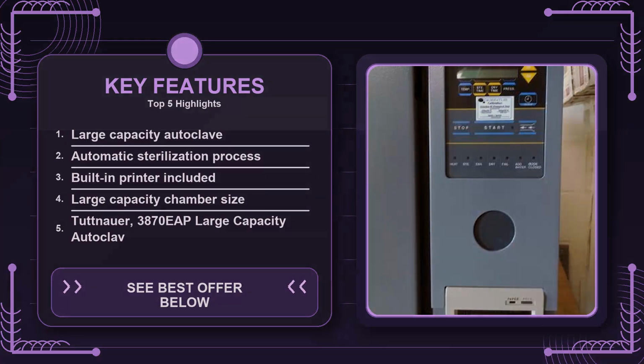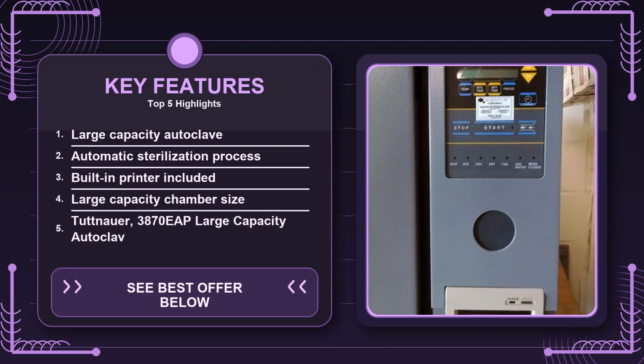However, the machine's cycle times are a bit longer than some of the newer, more compact models that boast rapid heat technology. In practice, you'll be looking at a typical sterilization run of around 30 to 35 minutes for a full load. If your workflow depends on turning around instruments within 10 minutes, you'll feel that lag. Conversely, if you can schedule your sterilization in batches, say, after every patient or every hour, the longer cycle becomes less of a bottleneck and more of a predictable rhythm.